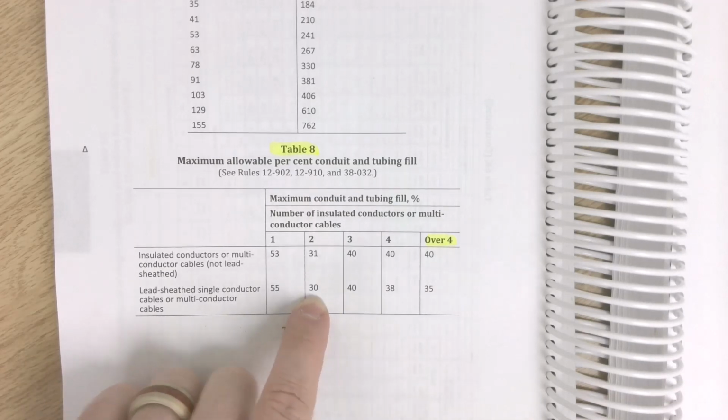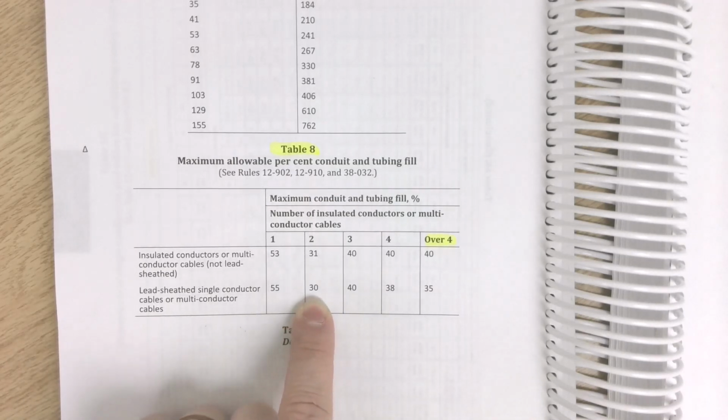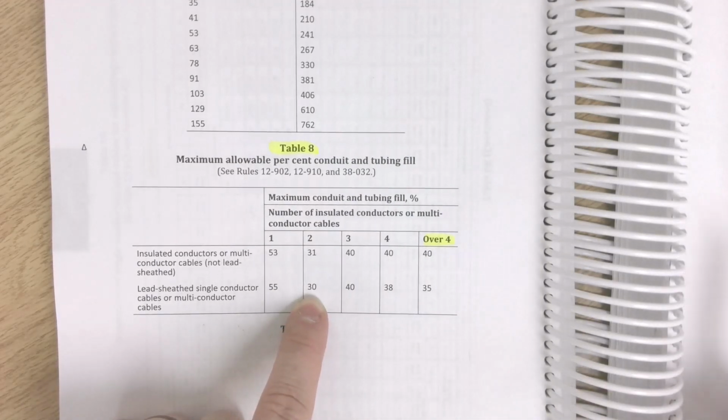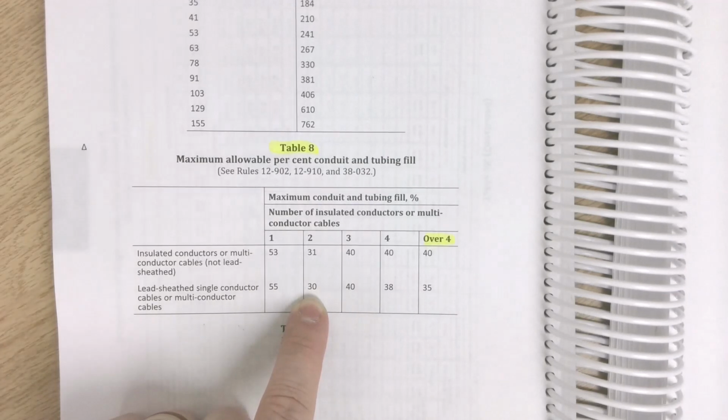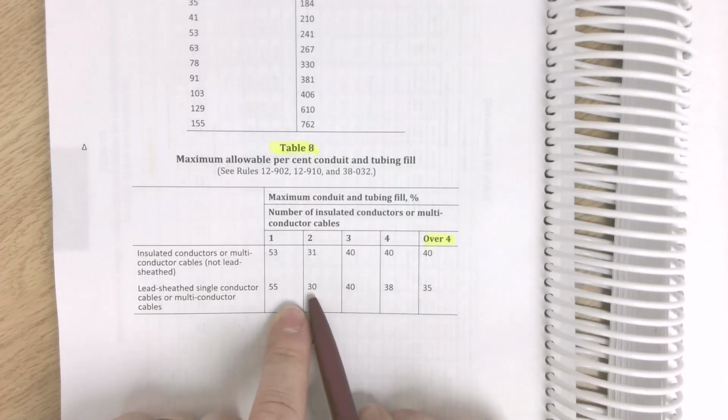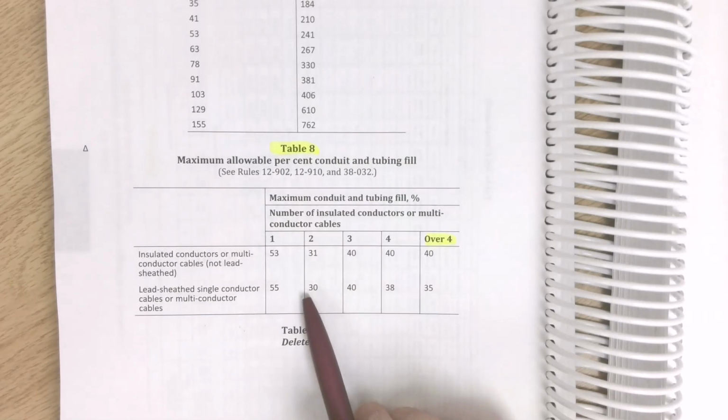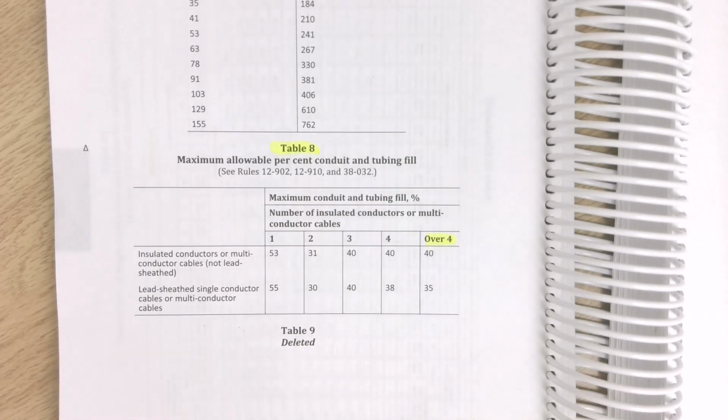Now, if it gave us a 30% conduit fill, I'm going to save you some time and tell you that none of the Table 9 tables have a 30% conduit fill table. So what you would do in that situation, if we didn't have the bond, let's say hypothetically it was a rigid metal raceway, and the rigid metal raceway functioned as the bonding means.